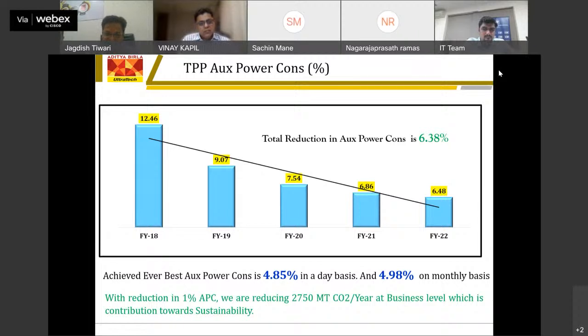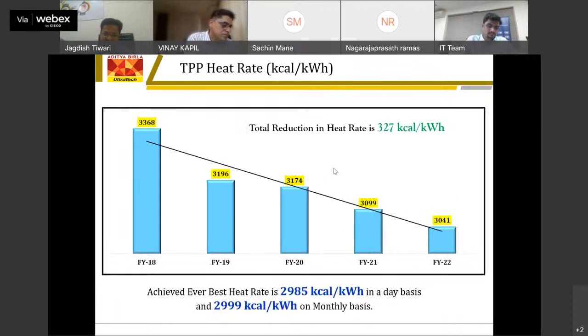Apart from the Dala unit, we are also leading the projects at our group level. In the previous year, we reduced auxiliary power consumption by 1% at group level. By reducing the 1% auxiliary power consumption, we have reduced near about 2750 metric ton CO2 per year at business level. So that is our contribution towards sustainability. Coming to the heat rate, sir, we have reduced heat rate by near about 327 kilocalorie per kWh, which contributed to reduction in carbon emission.